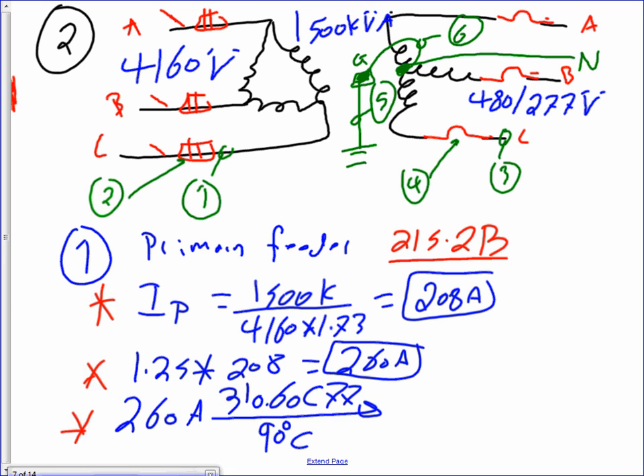I want to remind you guys that the cable that we're using on the primary side is a high voltage cable. Can I use the 310? Can I go to 310.15(B)(16)? Not anymore. I can't do that. I have to go to 310.60(C)(77), and you go to the 90-degree column, which is your default. I'm going to show you in a second how this table looks. When you go there, you're going to end up with 3 conductors of number 4 AWG, and the installation is called MV-90.